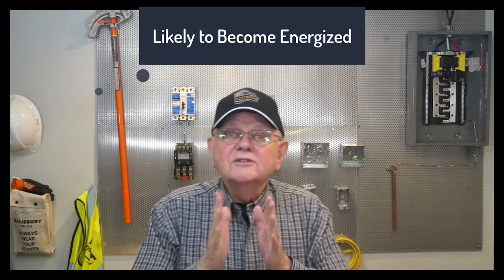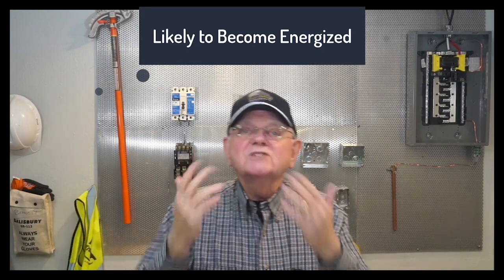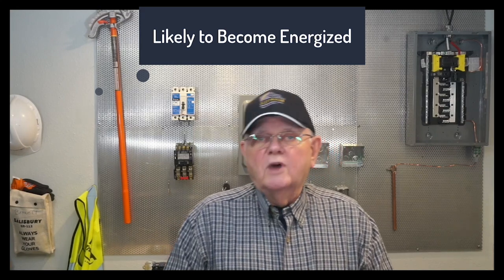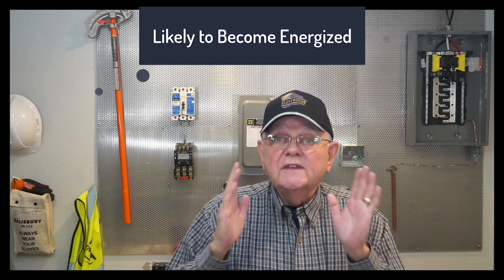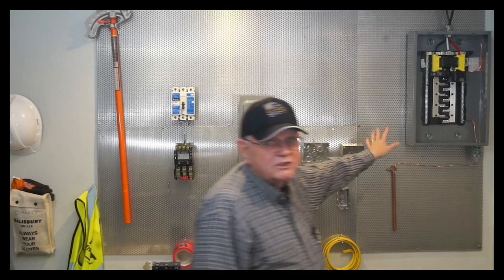The new definitions, a few of the new definitions, and I'll give you the ones that I kind of am partial to anyway. So, energized, likely to become. So, something that's likely to become energized. We use that term all of the time, don't we? If you think of ground faults, okay? Ground faults. So we have to bond to all of these metal components, don't we? Any normally non-current-carrying metal component that's likely to become energized during operation, we have to bond to it for safety. And so we've never had a term for likely to become energized.